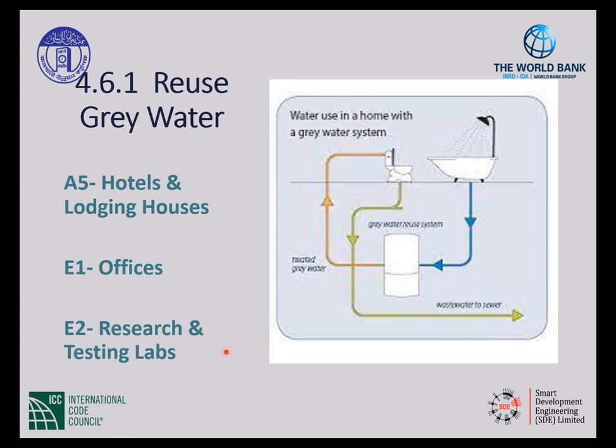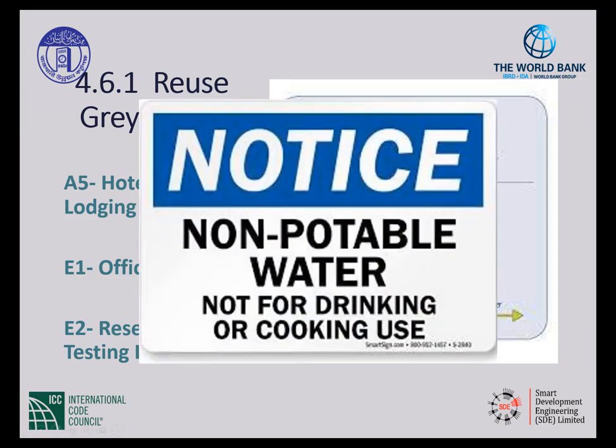What that's saying is gray water from the wash basins shall be reused in toilet flushing and/or irrigation after the filtration to ensure a BOD, a biochemical oxygen demand, level of less than 50. Such water shall not be considered potable.